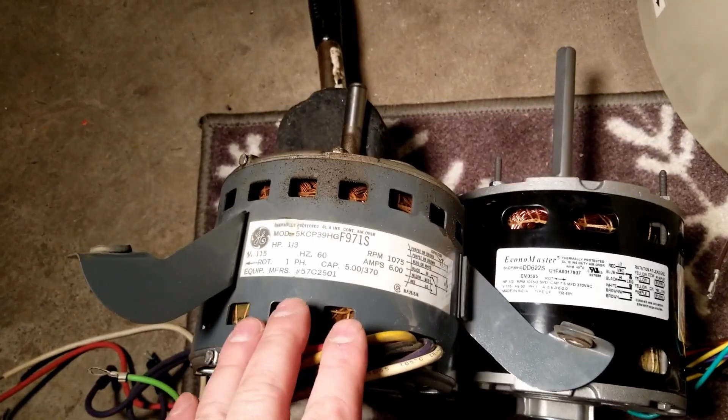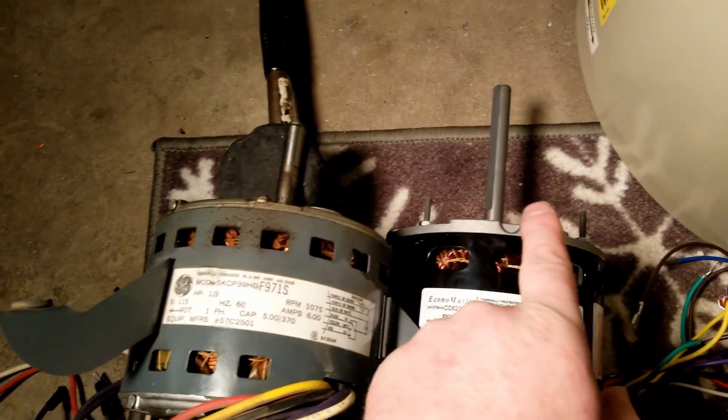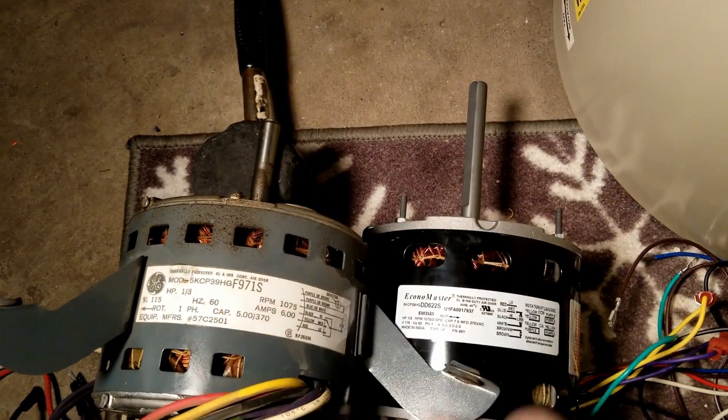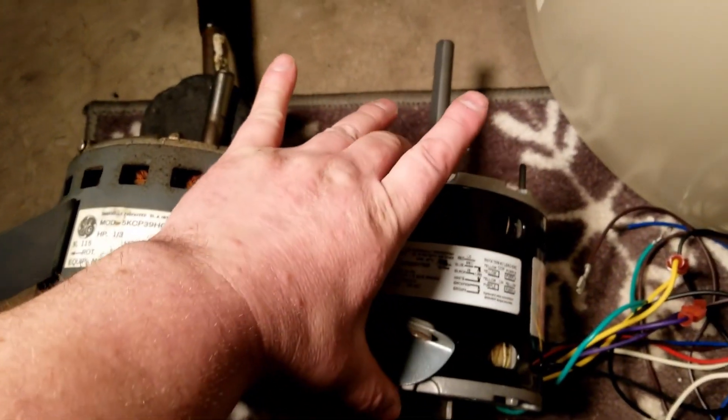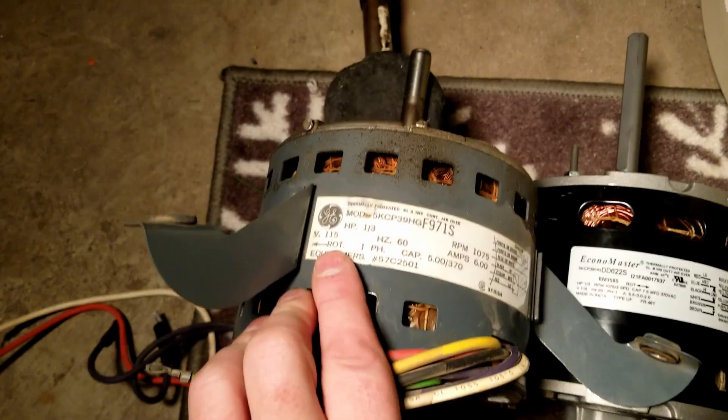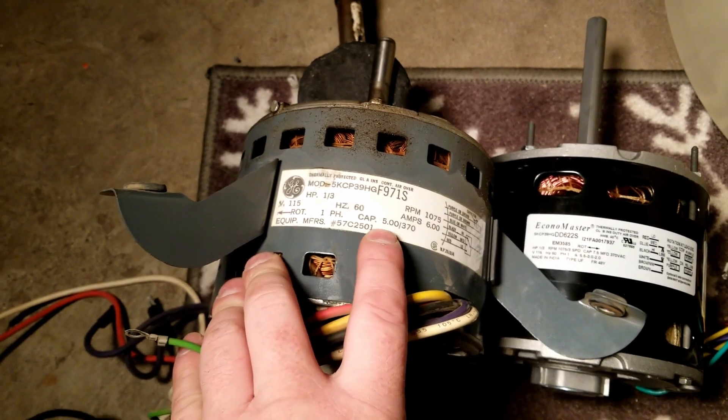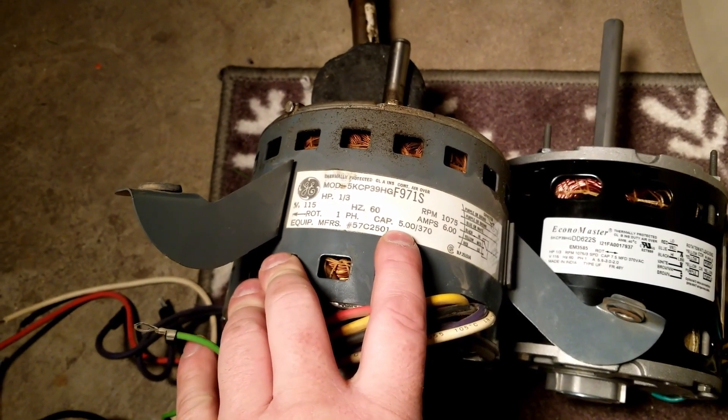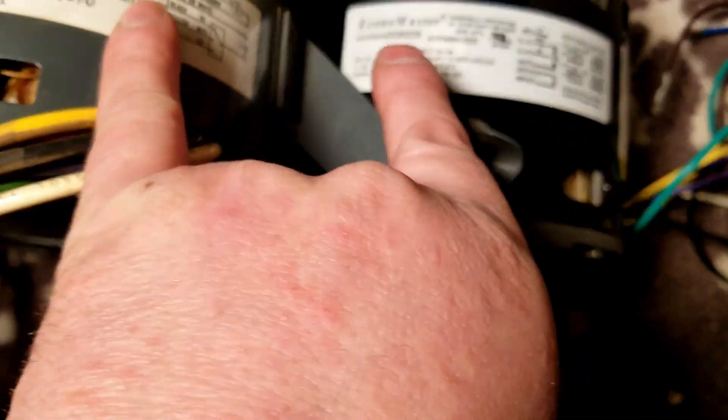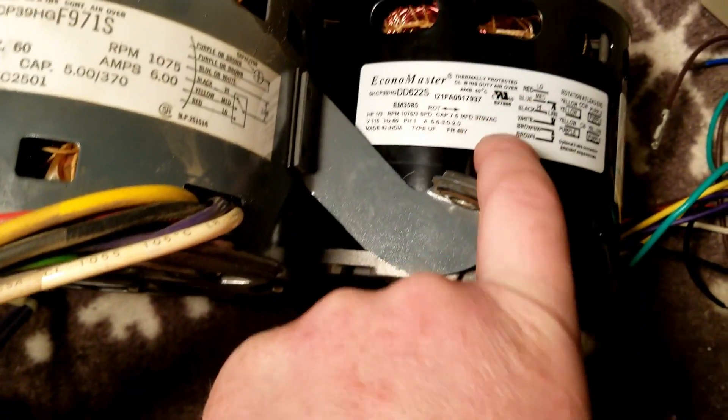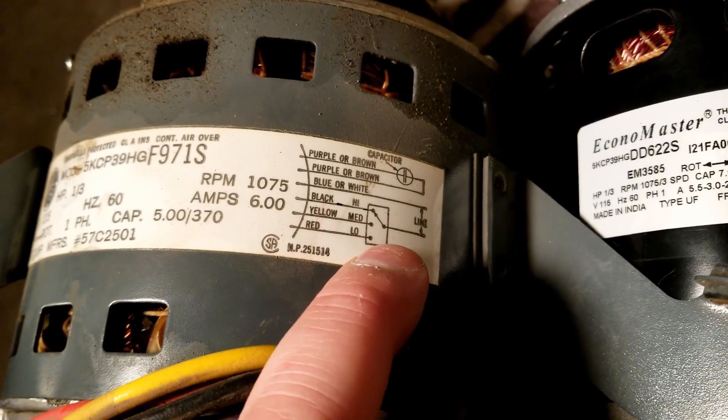Now we get our motors right next to each other. Couple differences right off the bat: the shaft on the new one is a lot longer than the old one. It's okay, we're just noting differences. This motor body's a little bit thicker than this one. Both of them one-third horse, 110 volt, 60 hertz. They always tell you what size capacitor to use: this one 5, this one 7.5. One-third horse, they're both the same RPM. This one's 0.5 amps less than this one.